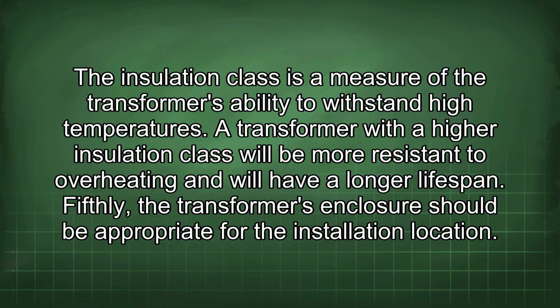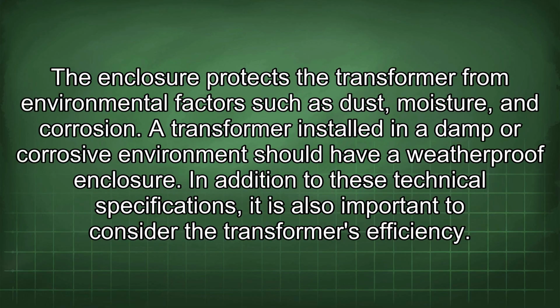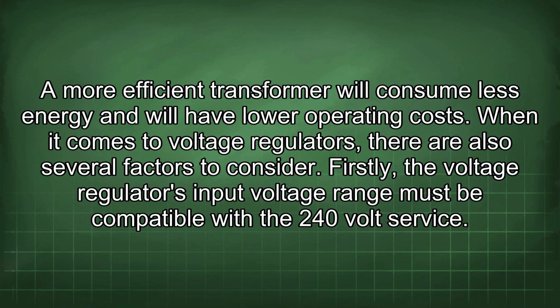Fifthly, the transformer's enclosure should be appropriate for the installation location. The enclosure protects the transformer from environmental factors such as dust, moisture, and corrosion. A transformer installed in a damp or corrosive environment should have a weatherproof enclosure. In addition to these technical specifications, it is also important to consider the transformer's efficiency. A more efficient transformer will consume less energy and will have lower operating costs.